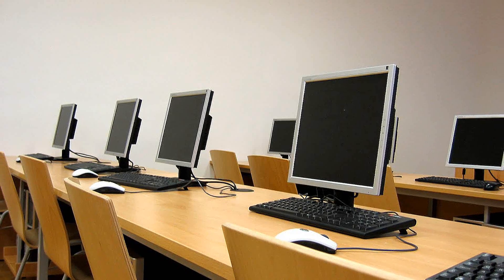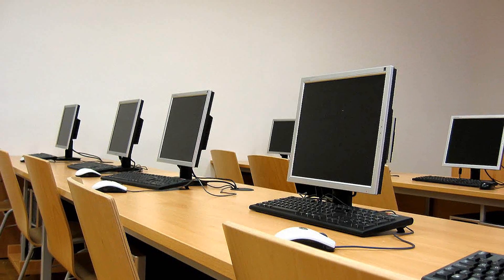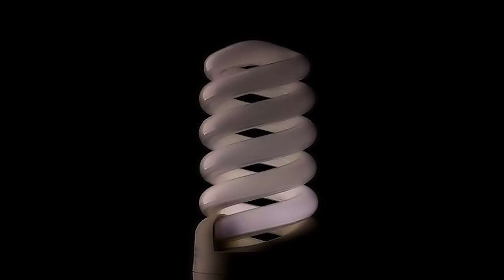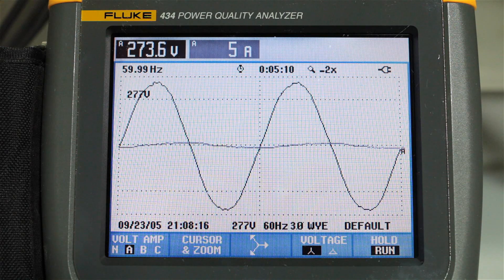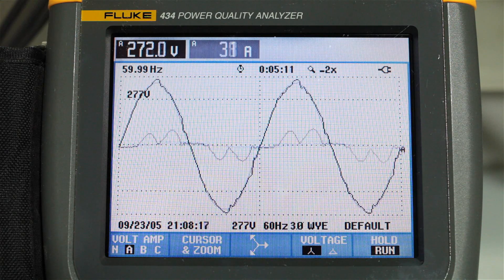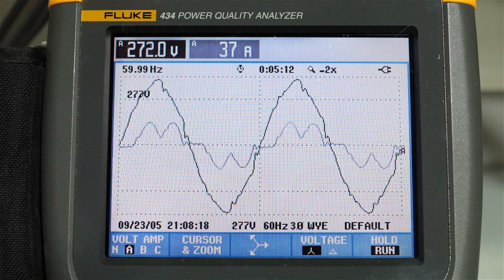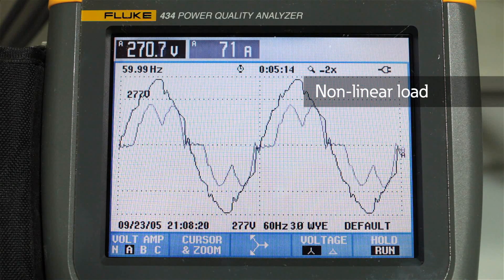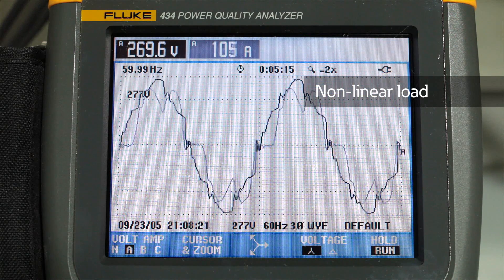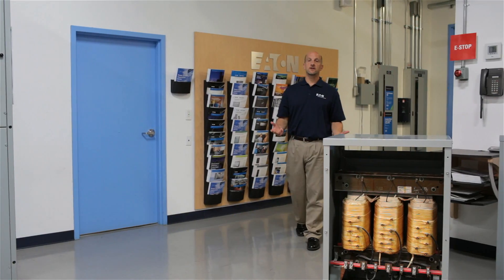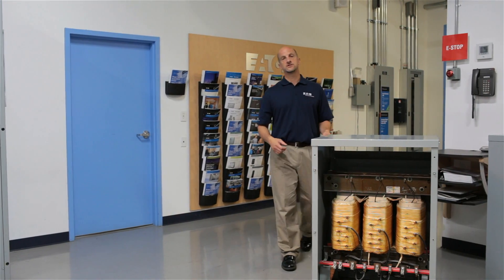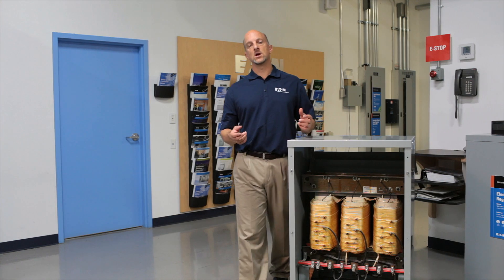Non-linear loads such as computers with switch mode power supplies, fluorescent lights, and variable frequency drives draw current that does not look similar to the voltage. This non-60 Hz current distorts the waveforms of the entire distribution system. The effects of harmonic distortion can appear in several ways.